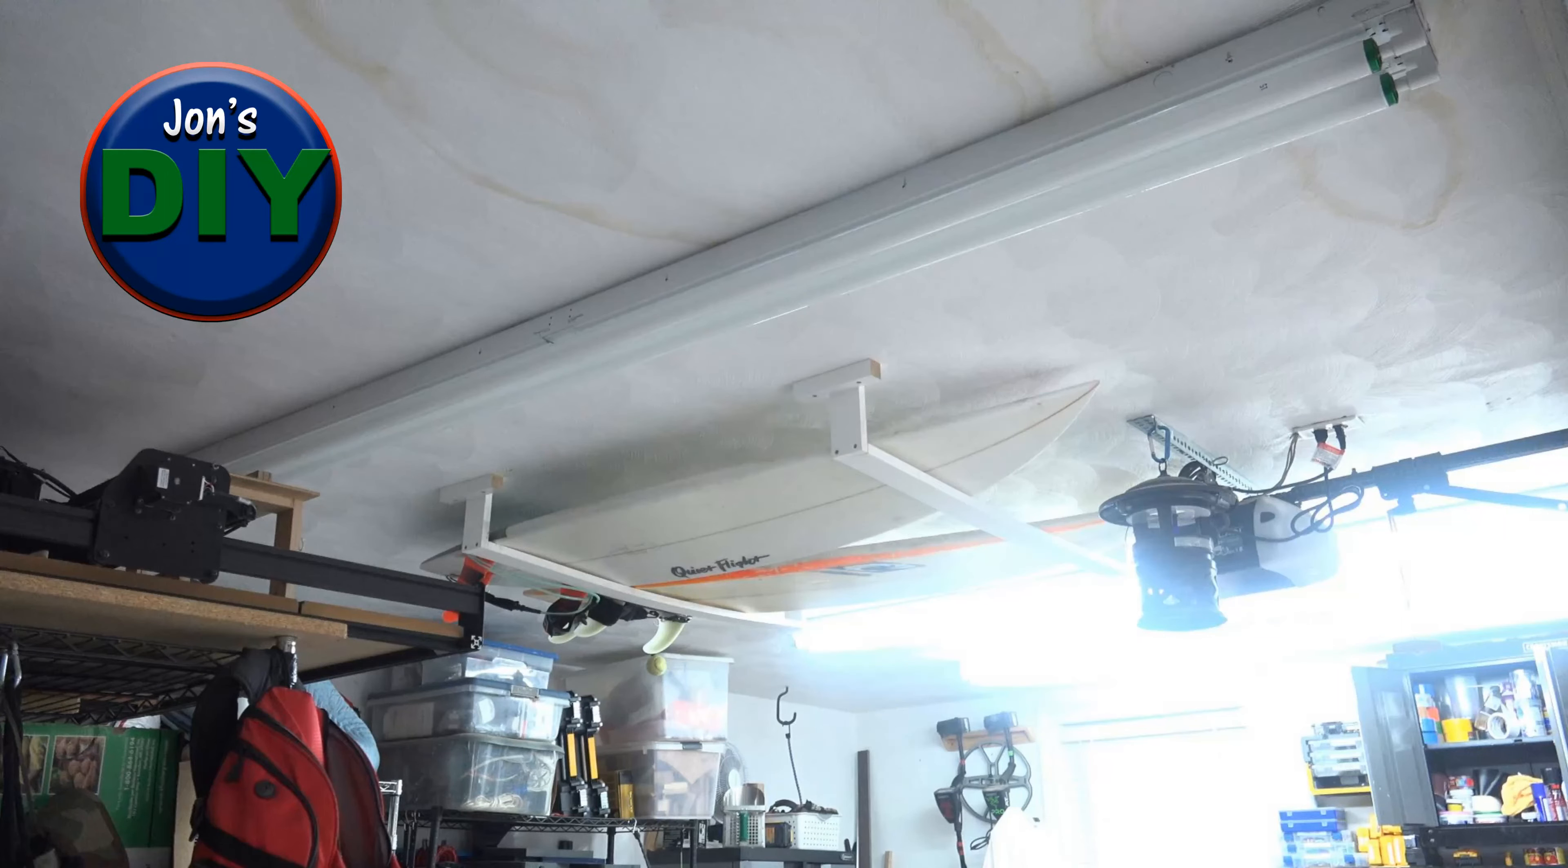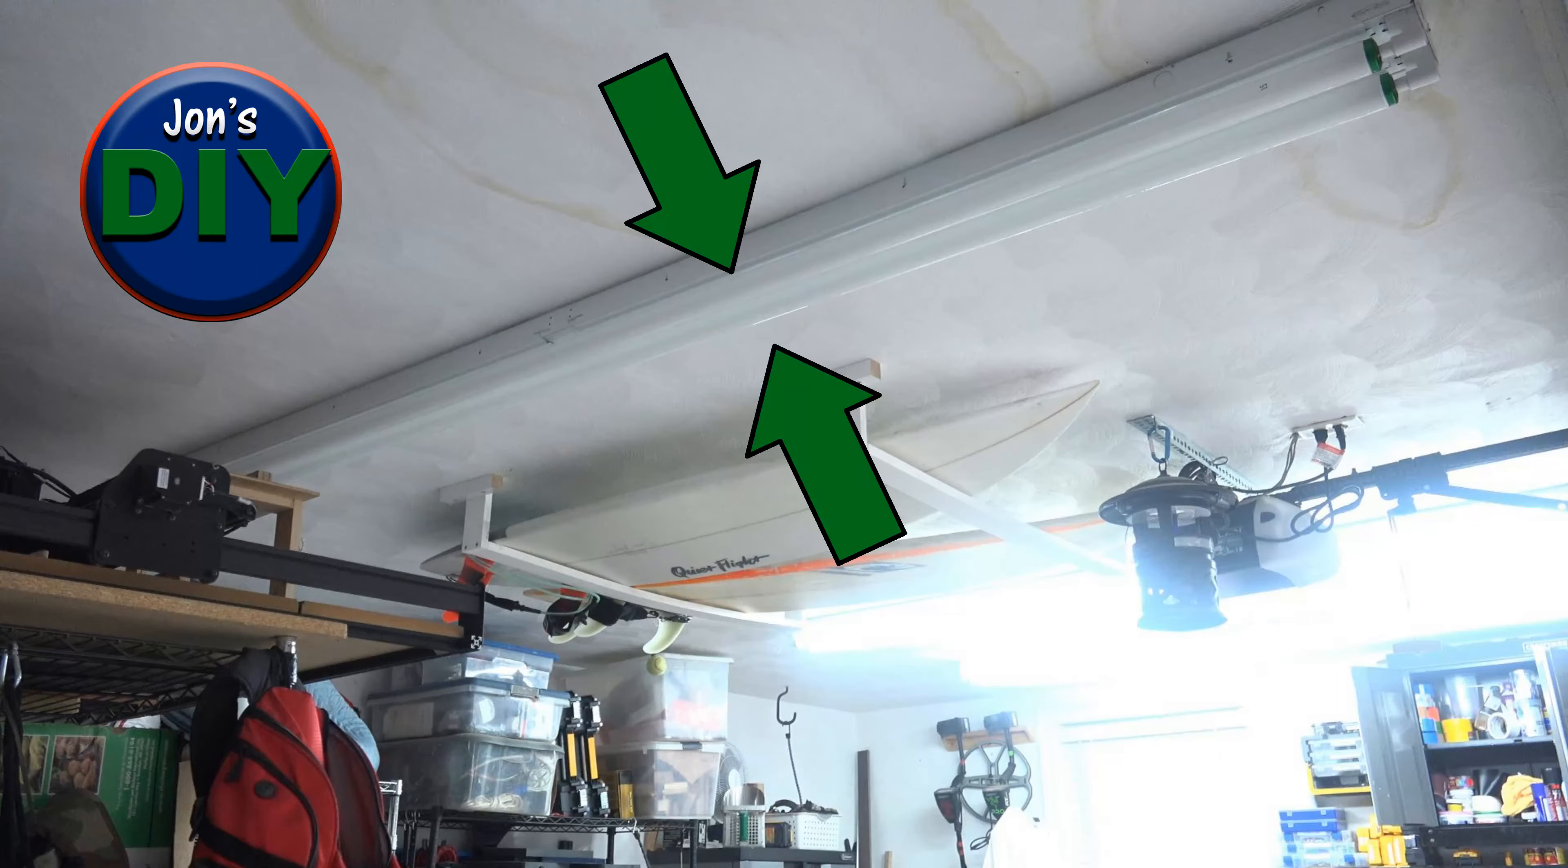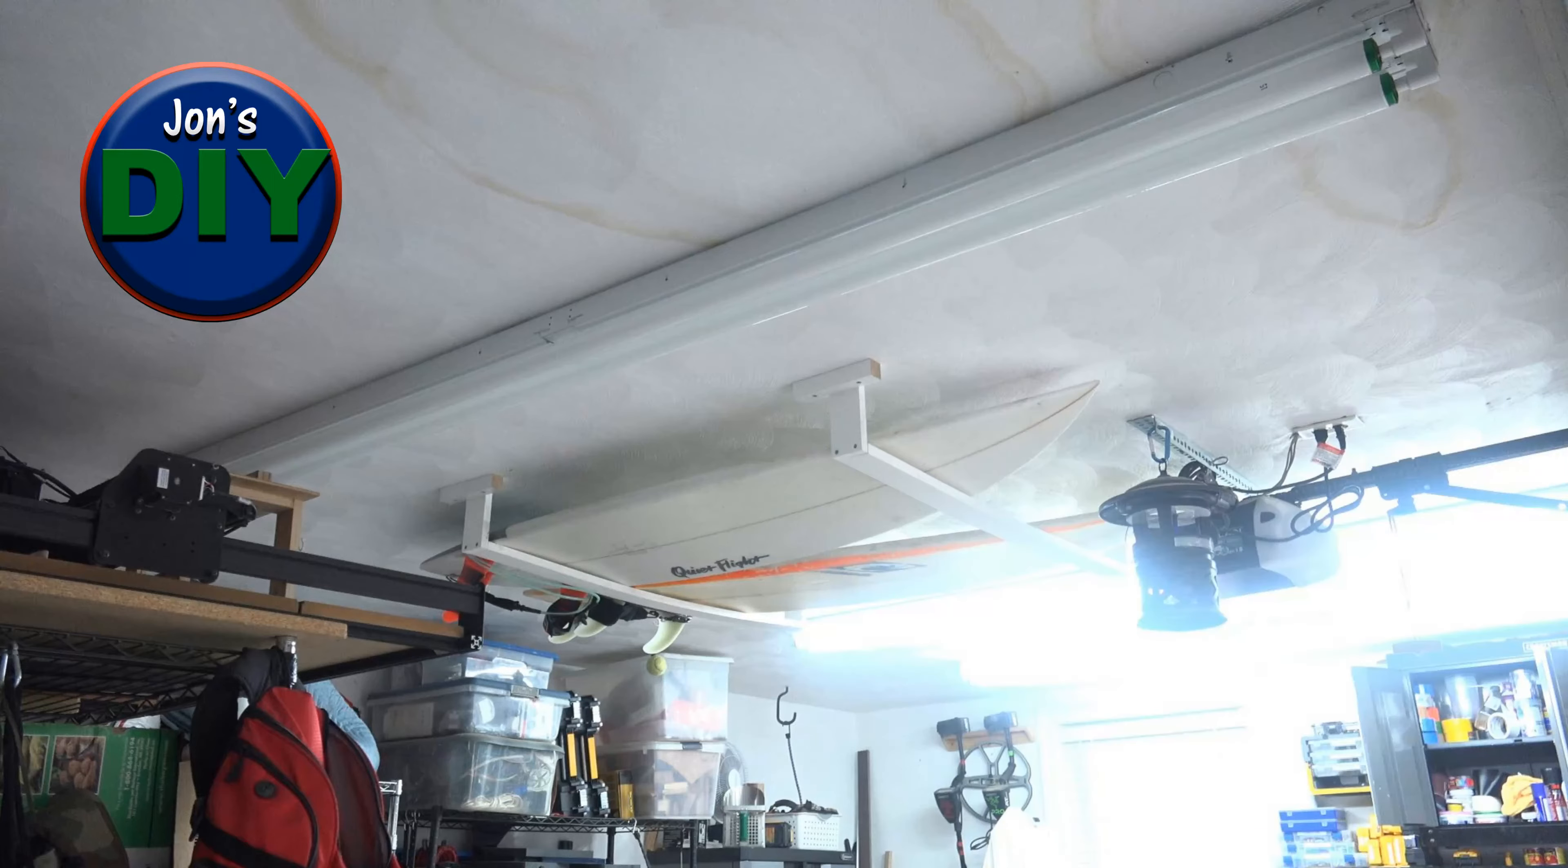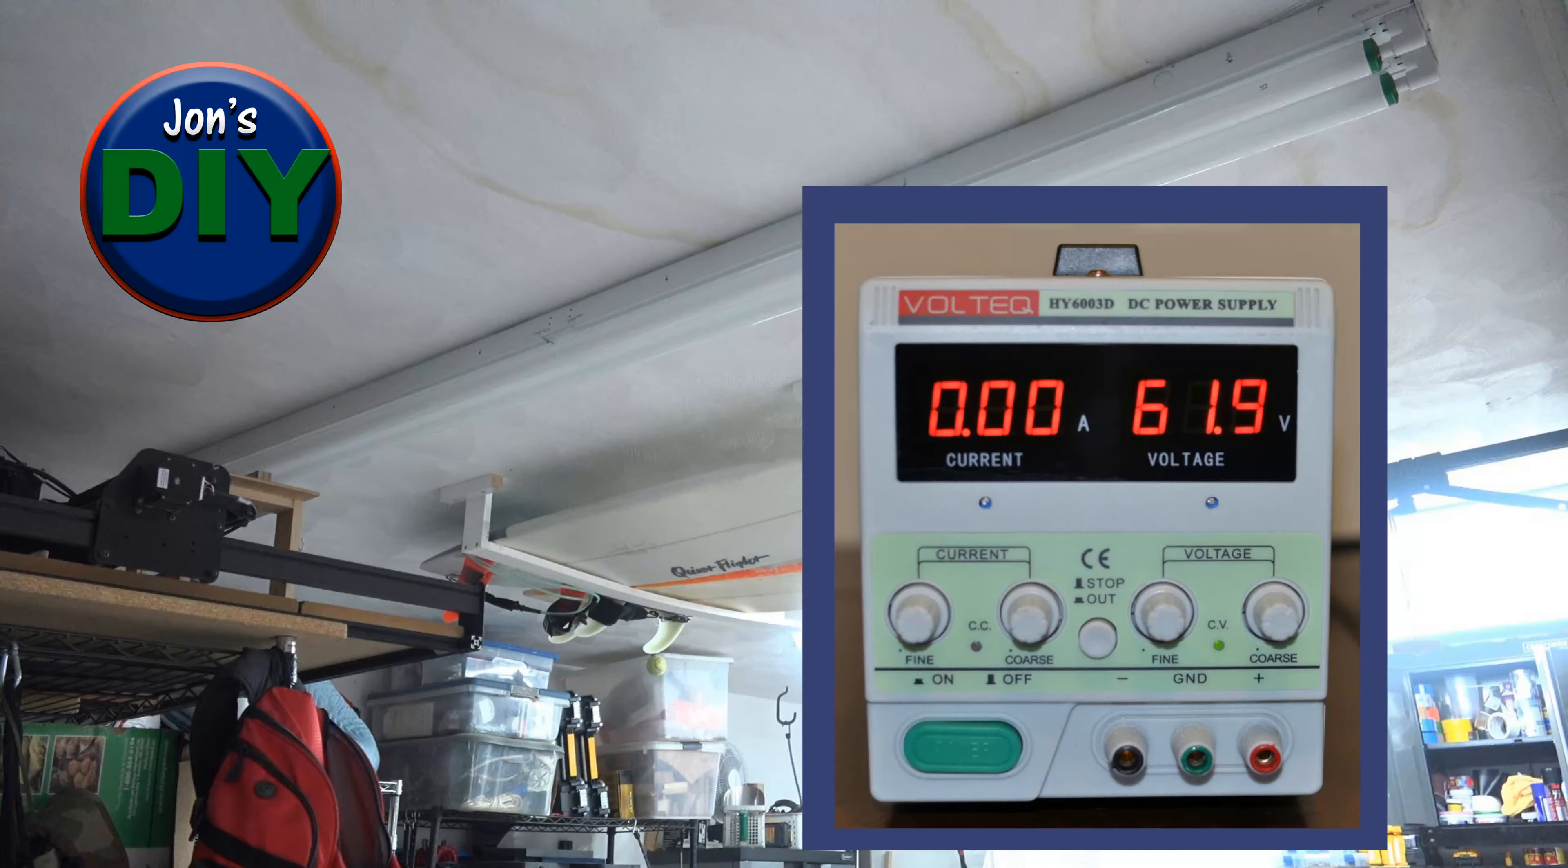Ballasts provide two functions: one, they establish the proper voltage for a continuous arc that all fluorescent bulbs need to be lit, and two, they keep the bulb lit by regulating the current so the light is stabilized and light output is continuous.